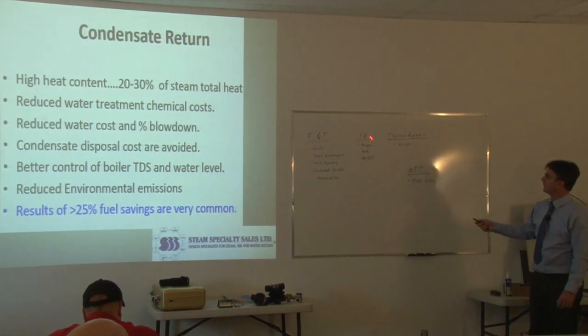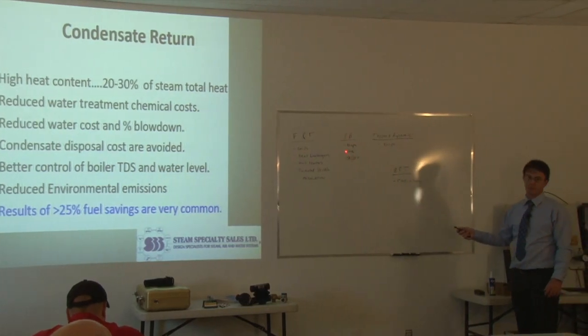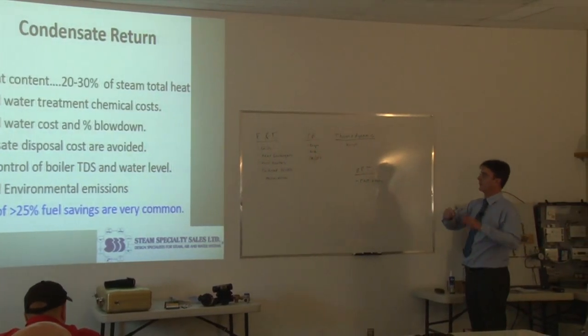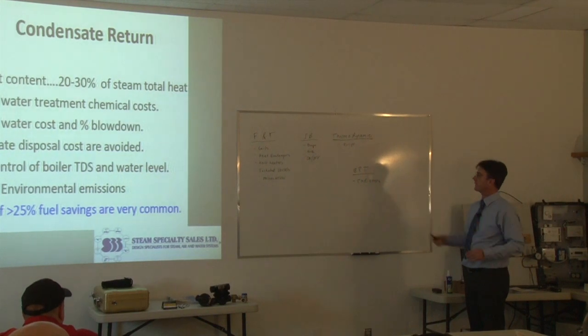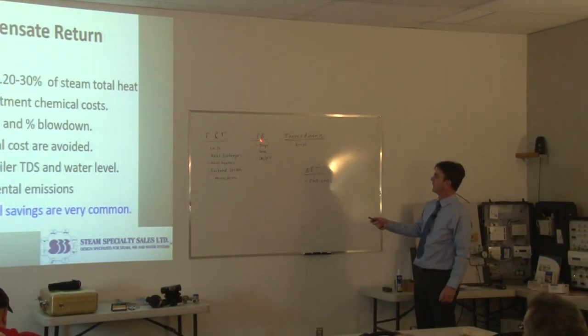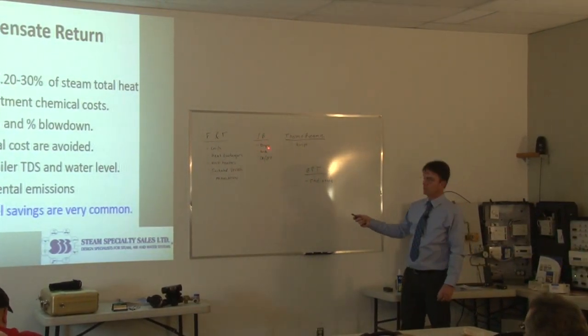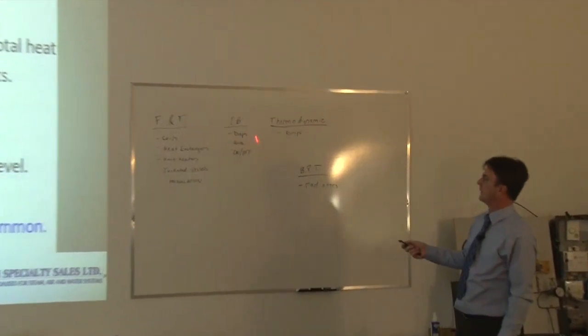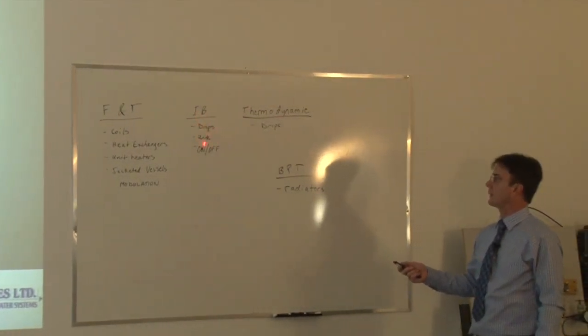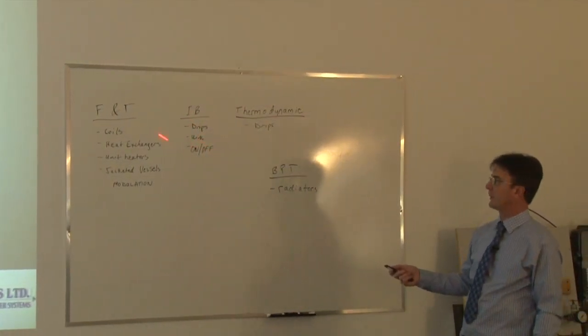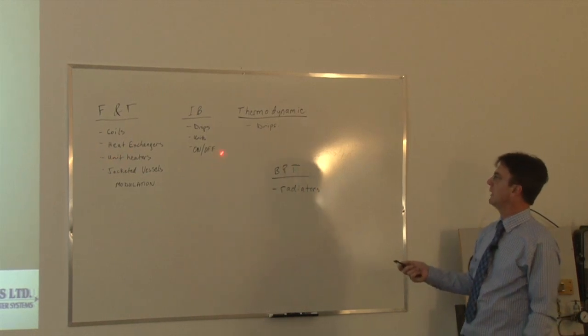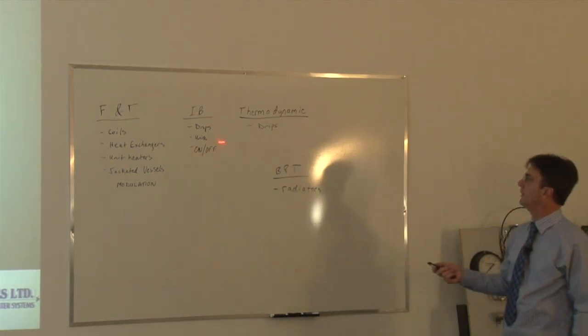Inverted buckets are typically used on drip applications. The drips are the end of lines, or anywhere there's a steam trap along a steam main — those are drip points to get rid of the condensate that builds up in the main. They can also be used on unit heaters, but I prefer to use an F&T. Anywhere there's an on-off application.